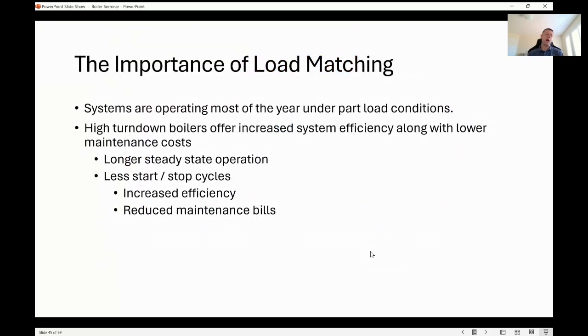Turn down ratio is how low your boiler modulates down to. So you guys have heard a 5-to-1 turn down ratio. That modulates from 20% fire to 100% fire. A 10-to-1 turn down ratio boiler will modulate from 10% fire to 100% fire, and a 25-to-1 turn down ratio, and that's the biggest one out there that I'm aware of right now, will go from 4% fire all the way to 100% fire. And basically that'll match the load requirements of the building much, much better.